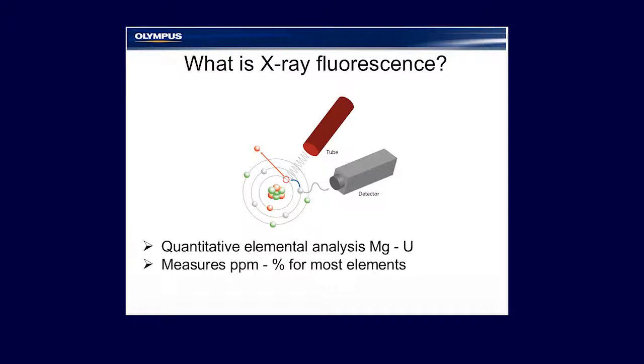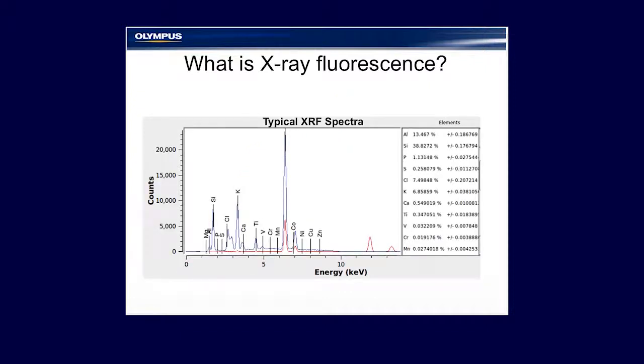XRF provides quantitative element analysis, typically magnesium through uranium. It can measure from the PPM level to percent level for most elements. On this next slide, we're showing the user interface — how the operator first sees the data output from the instrument. It consists of a graphic output, and to the right-hand side of the slide, it also gives you elemental breakdown, concentration, and statistical analysis. That's the output for X-ray fluorescence.